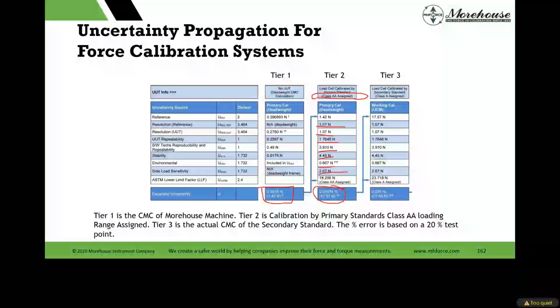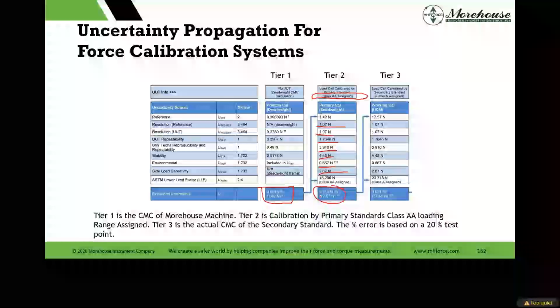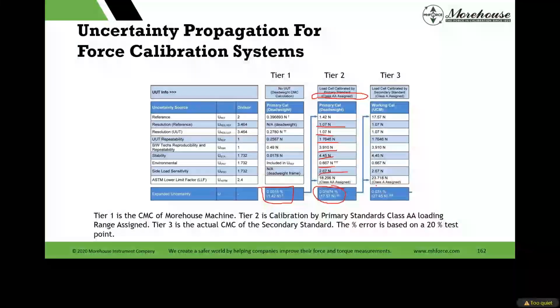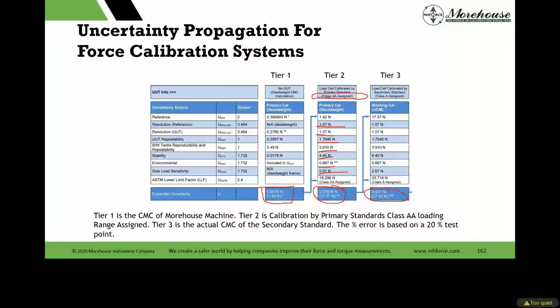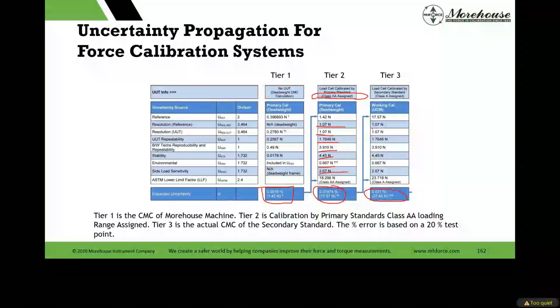And then we said, okay, let's use that UCM to calibrate another load cell and see how good we can get. Well, we cheated a little bit. When I say we cheated, we basically used the same exact repeatability numbers. You see these? We did this intentionally, and it's in the paper. The reason we did it intentionally is to say, this is how uncertainty propagates. This is the absolute best we can get.